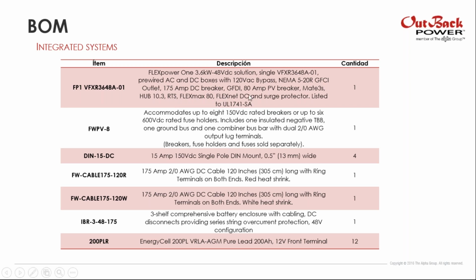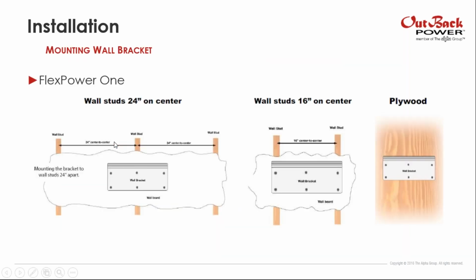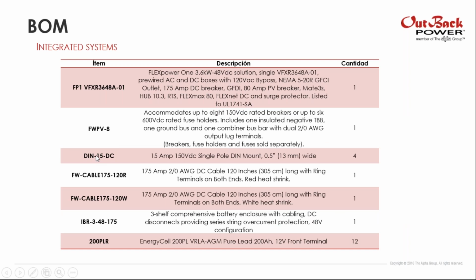So it is really easier for you to acquire these kinds of systems. So your BOM is reduced to the FLEXpower, the combiner box, I'm sorry, the breakers for the PV array, two cables for the batteries, and the batteries and the enclosure. And if you buy batteries like our RE high capacity solution, you will have the battery integrated. So this BOM is easier to order than the other one with separate components.